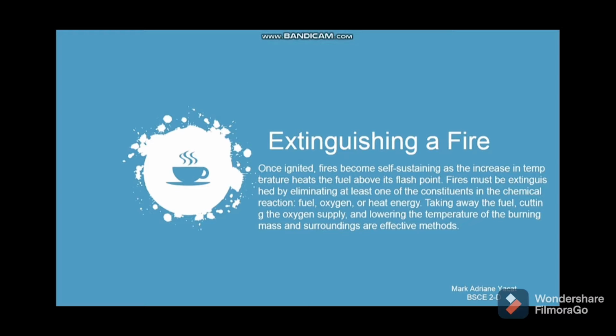Extinguishing a fire. Once ignited, fires become self-sustaining as the increase in the temperature heats the fuel above its flash point. Fires must be extinguished by eliminating at least one of the constituents in the chemical reaction, namely fuel, oxygen, or heat energy. Taking away the fuel, cutting the oxygen supply, and lowering the temperature of the burning mass and surroundings are effective methods.